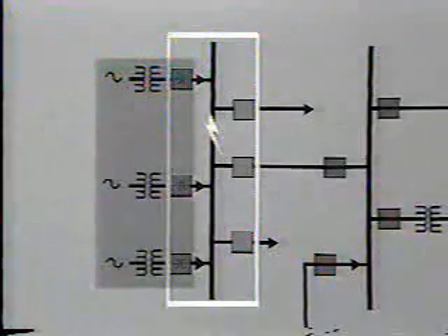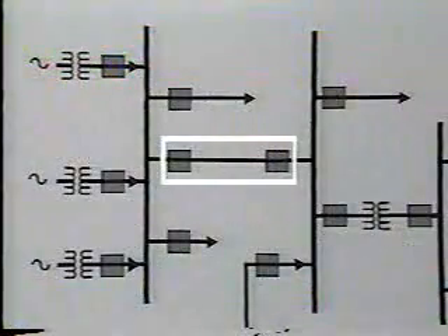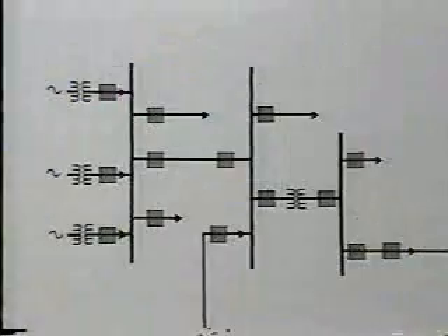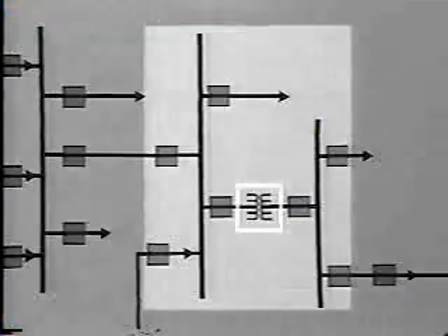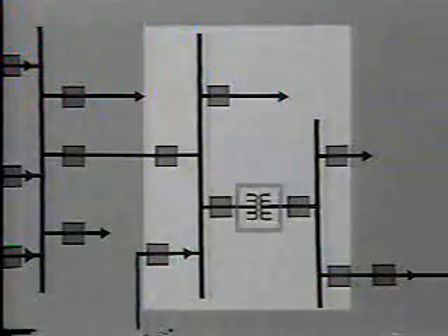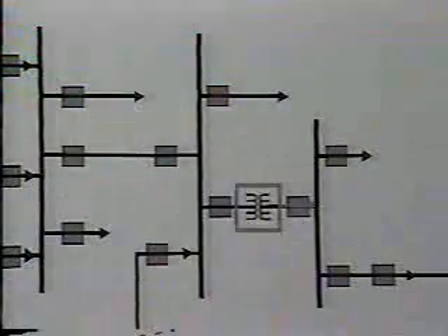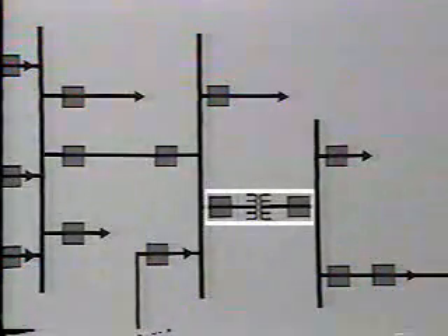You can see that these generator breakers will operate either for a fault within the generator zone or a fault in the bus zone. The next area in this particular power system is the transmission line zone, and once again, this overlaps the bus zone at either end. Hence, these breakers will open for a line fault and also for a fault on its respective bus. In this particular substation, we have a transformer which reduces voltage down to distribution level and feeds the distribution bus. So we have a transformer protection zone, and this overlaps the bus zone on either side.